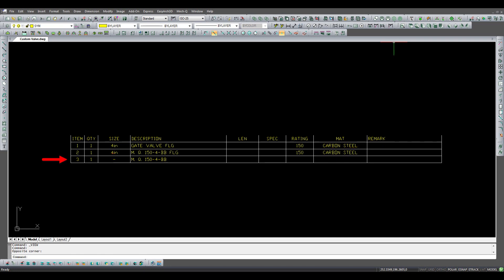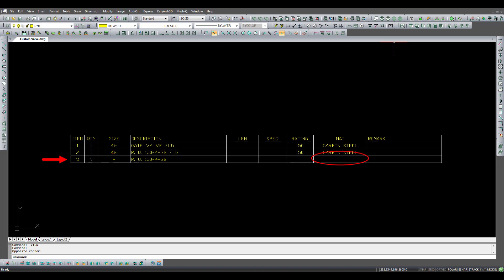Compare that with item number three. This valve is a user-defined block that was tagged using the object option. While it does use the part number, it lacks the nominal diameter, rating, and material. This missing information would have to be added manually to the title block and would not be available for data extraction.